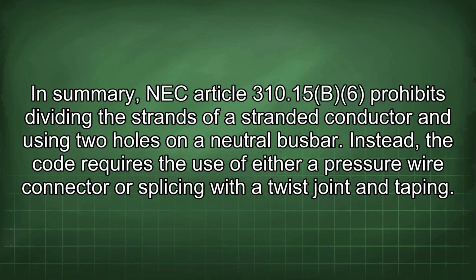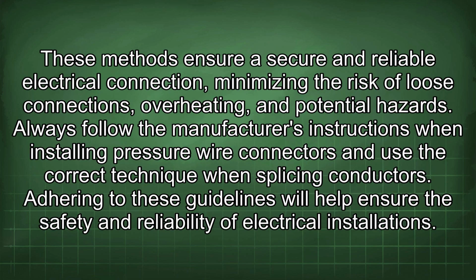In summary, NEC Article 310.15(B)(6) prohibits dividing the strands of a stranded conductor and using two holes on a neutral busbar. Instead, the code requires the use of either a pressure wire connector or splicing with a twist joint and taping. These methods ensure a secure and reliable electrical connection, minimizing the risk of loose connections, overheating, and potential hazards. Always follow the manufacturer's instructions when installing pressure wire connectors and use the correct technique when splicing conductors. Adhering to these guidelines will help ensure the safety and reliability of electrical installations.